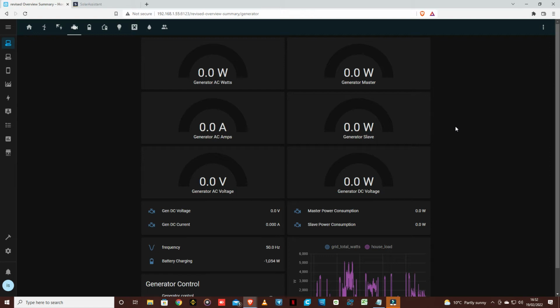Two is that if you have no real control over your generator, the more you load, the slower it will bog down, like driving around with your handbrake on, right? Then as the frequency drops, your Sunny Island will start to back off the amount of watts or amps applied to that generator, and you can end up with this backwards and forwards.